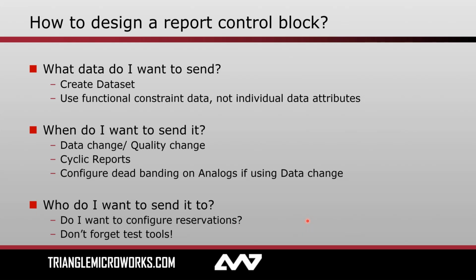The next thing you'll need to think about is deciding, when do I want to send the data? So commonly, you'll want to use data change and quality change. If any of the data in my data set updates, I want to know about it. That's the whole point of a report, an event-driven scenario. There might be some cases where, if you have analog data, you want to do cyclic reports because that data is changing constantly. It's no longer event-driven per se, but just every 3 seconds, send me the voltage. Or you could still use a data change or quality change method and configure dead banding or limits.